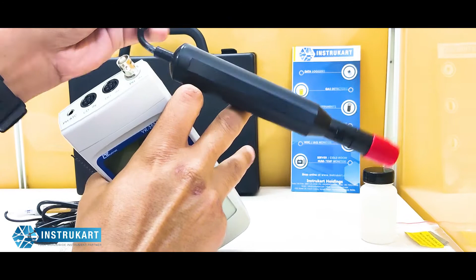Now coming to the probes one by one, if I want to show you, this is an ORP probe, which is also called oxidation reduction potential probe. Now as you can see, this is having 1 point input which goes into this particular socket. Now at the same time you can also use the pH probe. There's one more for conductivity which fits in here. This is a conductivity meter or the probe, and there's one more which is for dissolved oxygen. And this also fits in here.